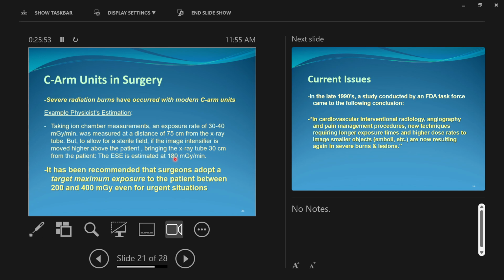And you go to 10 or 15 minutes of fluoroscopy time, and now you're well into the range where you can start causing skin burns. Okay? So these things add up very quickly. Distances matter a lot, the distance that we are from the source of radiation. And in C-arm, this C-shaped thing that we have is such a fixed thing that if I want to move my receptor farther, my x-ray tube is going to end up closer to my patient. So I have to keep an eye on that. Luckily, that's not a concern for limited radiography. It's just something that you should keep in mind.